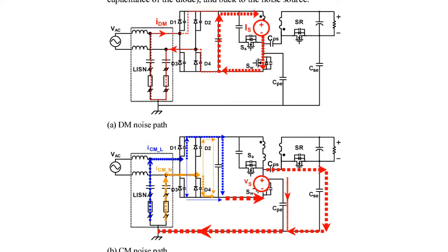Common mode noise in terms of AC power is the noise signal between the neutral and the ground conductor. This should not be confused with normal mode noise, which is referenced between the line, hot, and the neutral conductor.